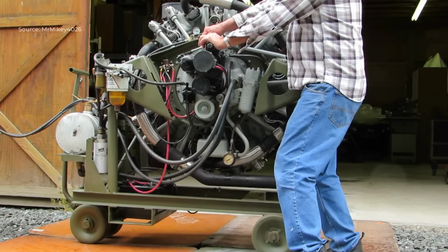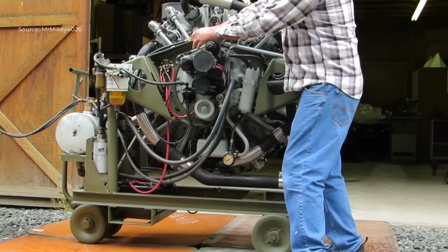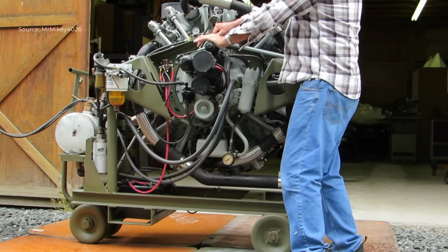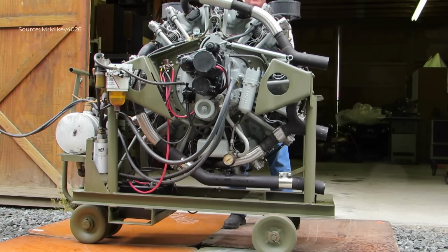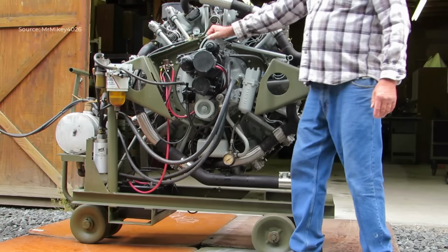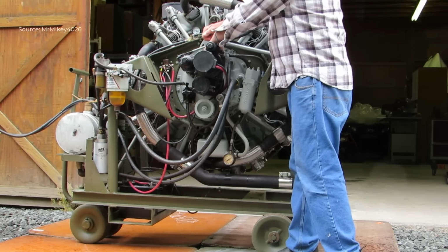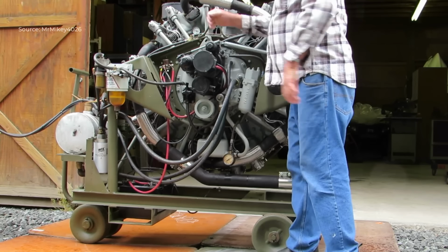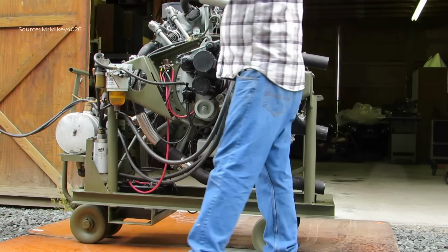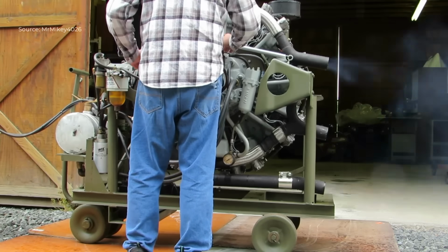Before startup, the procedure emphasizes careful preparation. The fuel pump is switched on first, followed by engaging the compression relief. The engine is then rotated several revolutions to confirm that no oil has accumulated in the cylinders, preventing potential damage. Once checks are complete, the inertia starter is wound up and engaged, bringing the radial diesel to life.